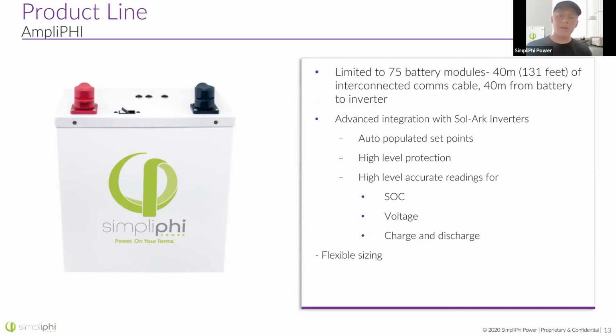You are limited to 75 battery modules in parallel, as there is a Cat5 cable connecting them, and after a certain distance, the signal between the batteries is just not as strong. So you're limited to 75 batteries in parallel in this type of system. Now this allows you to integrate our battery with Solar Converters, SMA Sunny Island inverters, and our new inverter, the SimpliPhi ESS. What is going to happen here is many of the battery related set points are going to auto populate so that the inverter is going to know how large the battery bank is, how quickly it can be charged, the charge voltages and low voltage cutoffs, etc.